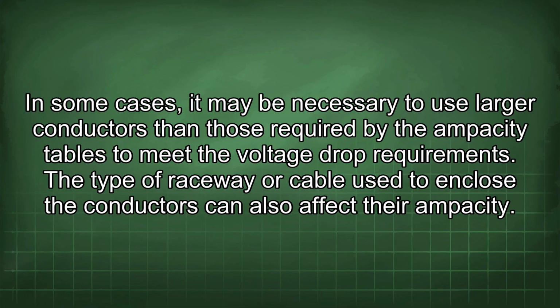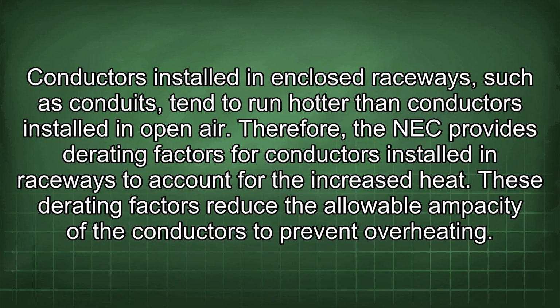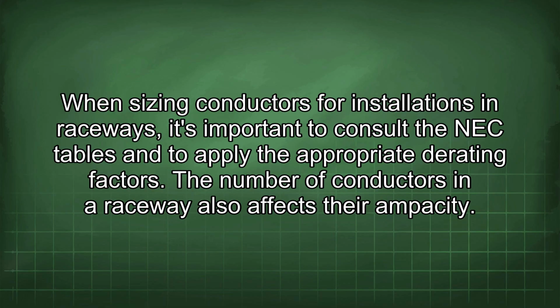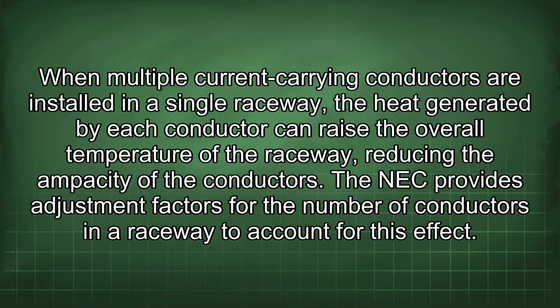The type of raceway or cable used to enclose the conductors can also affect their ampacity. Conductors installed in enclosed raceways, such as conduits, tend to run hotter than conductors installed in open air. Therefore, the NEC provides derating factors for conductors installed in raceways to account for the increased heat. These derating factors reduce the allowable ampacity of the conductors to prevent overheating. When sizing conductors for installations in raceways, it's important to consult the NEC tables and to apply the appropriate derating factors. The number of conductors in a raceway also affects their ampacity. When multiple current-carrying conductors are installed in a single raceway, the heat generated by each conductor can raise the overall temperature of the raceway, reducing the ampacity of the conductors.